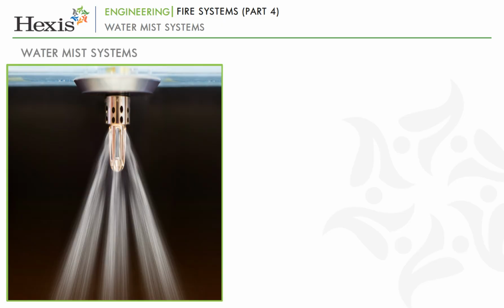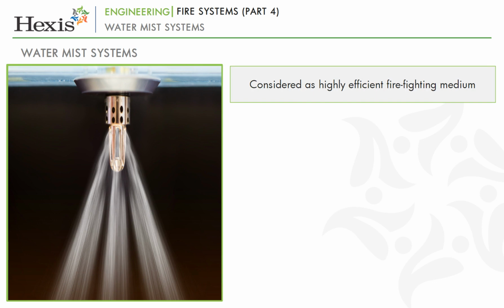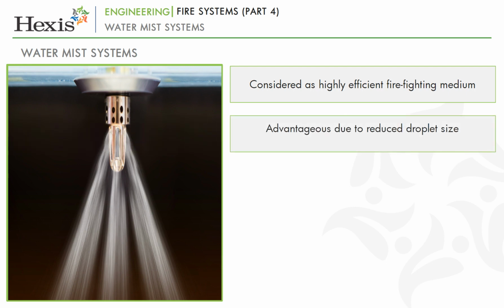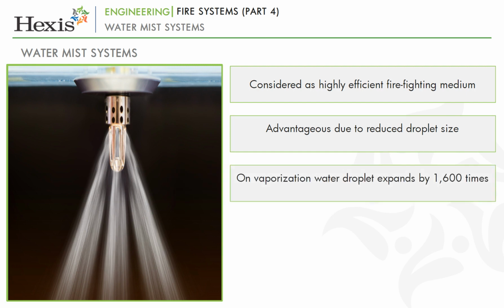Now let's look at the water mist systems. Water mist is a versatile and highly efficient firefighting medium. What differentiates water mist from traditional water-based systems is its reduced droplet size. When a droplet of water vaporizes, it expands by some 1,600 times.